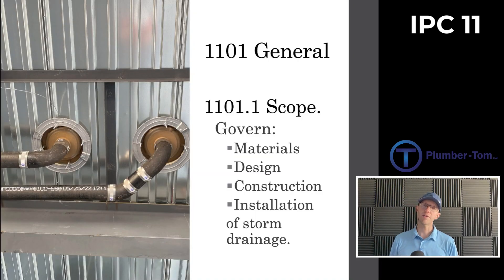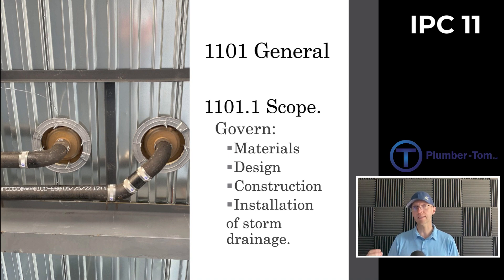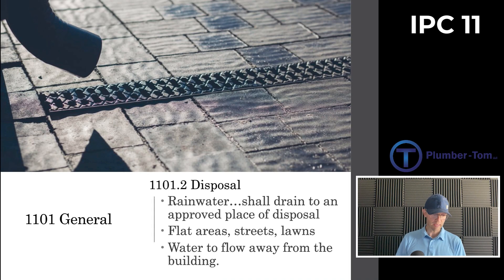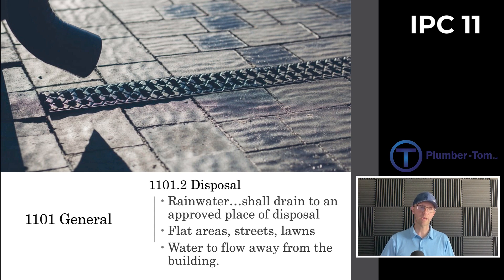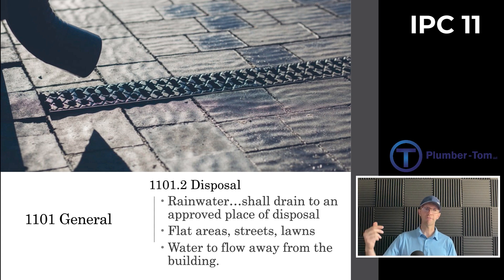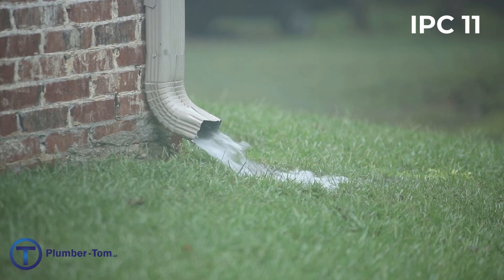Let's get into the code. We begin with Section 1101, General. 1101.1 gives us the scope, stating that the provisions of this chapter shall govern the materials, design, construction, and installation of storm drainage. 1101.2 talks about disposal of rainwater, specifically stating that rainwater shall drain to an approved place of disposal — flat areas, streets, lawns — but definitely the water needs to flow away from the building.